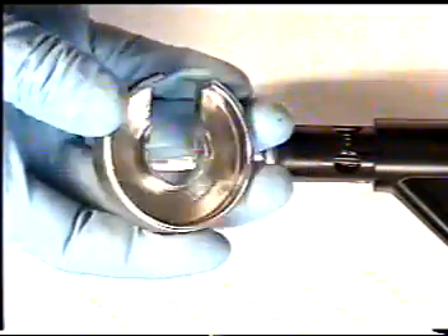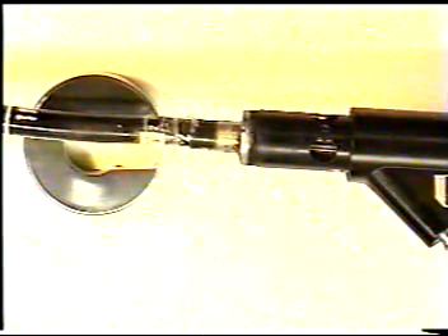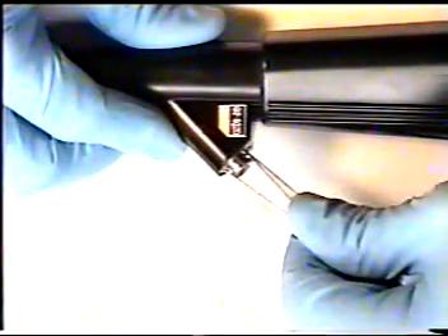Unscrew and pull down the first body section ring. Pull this piece down, which includes O-ring, to the 80 centimeter mark on the insertion tube. Using your C-wrench tool, slide tool up and over insertion tube onto body section. With the tool, feel for the two indentation marks in the body section ring and unscrew counterclockwise. This will unscrew ring, enable to pull down the body control cover. Using a pair of heavy-duty tweezers, unscrew the biopsy port retaining ring.